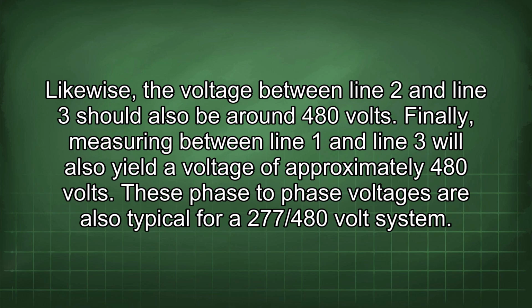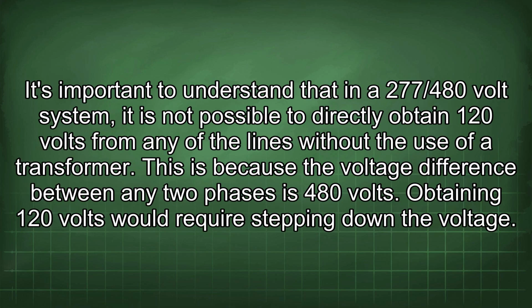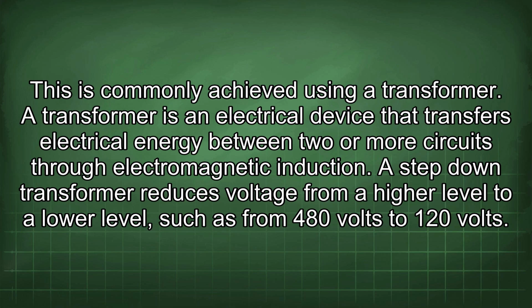These phase-to-phase voltages are also typical for a 277/480 volt system. It's important to understand that in a 277/480 volt system, it is not possible to directly obtain 120 volts from any of the lines without the use of a transformer. This is because the voltage difference between any two phases is 480 volts. Obtaining 120 volts would require stepping down the voltage. This is commonly achieved using a transformer.